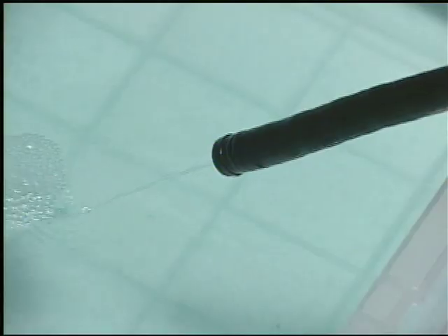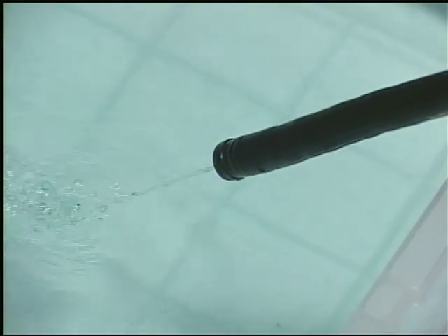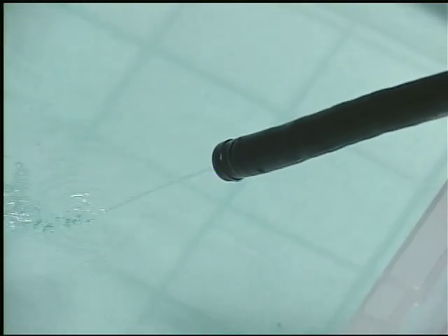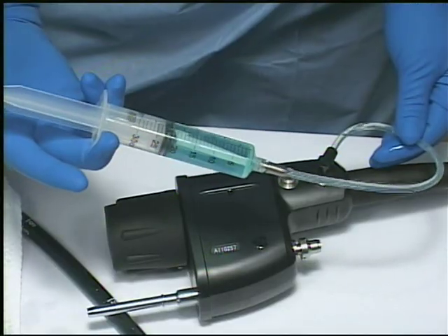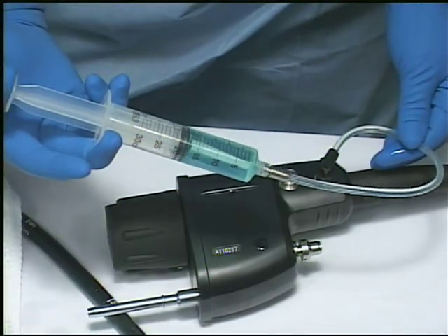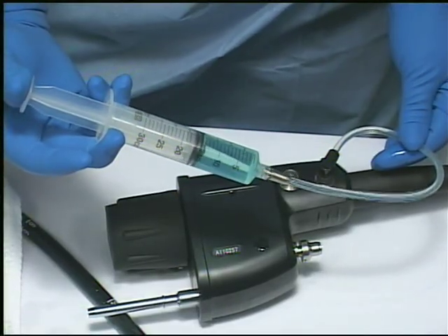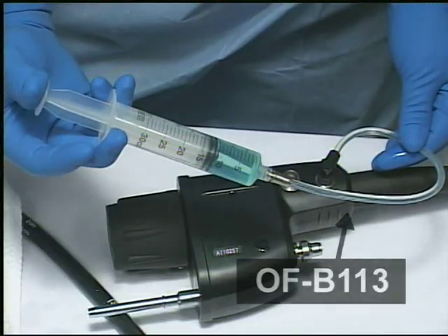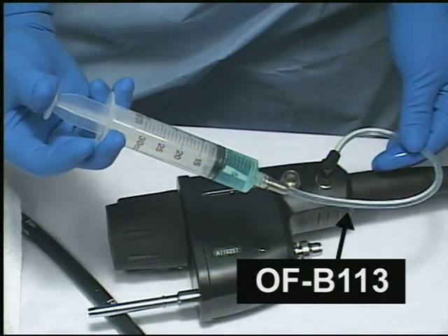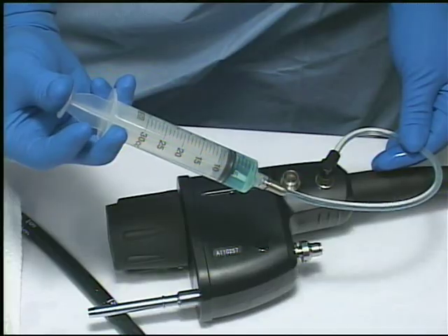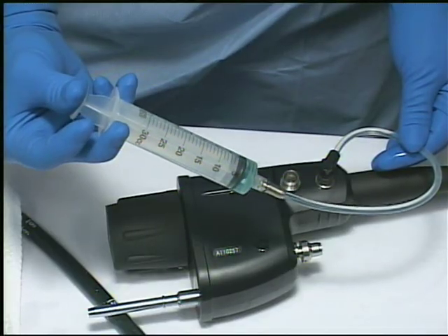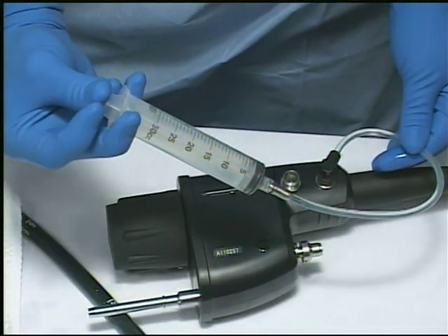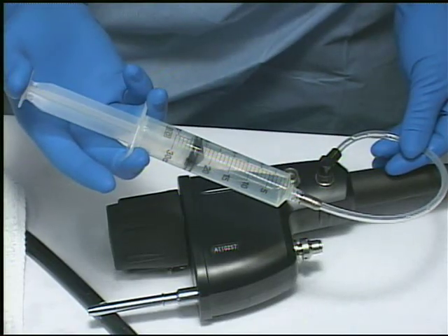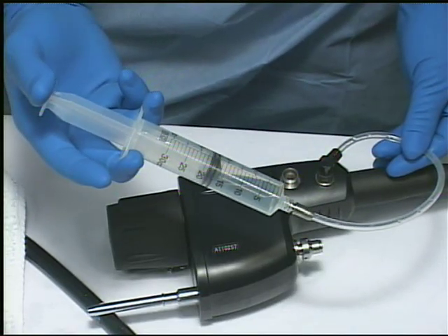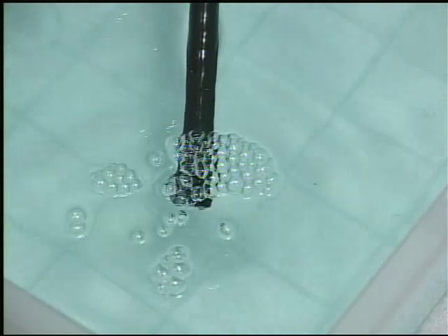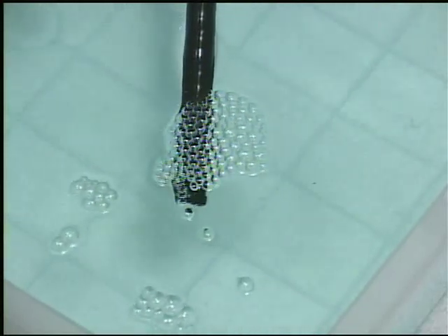During pre-cleaning, immediately after the procedure, the forward water jet channel should be flushed with water or enzymatic detergent solution. Using a syringe or irrigator, flush solution through the irrigation tubing OFB 113 directly into the forward water jet port located on the PVE connector. Purge the channel with the syringe and air several times to force any residual solution out of the channel.